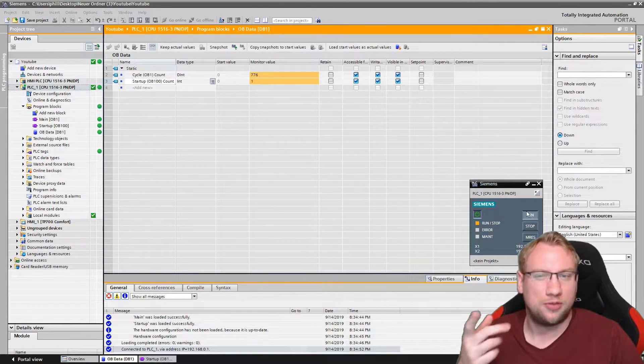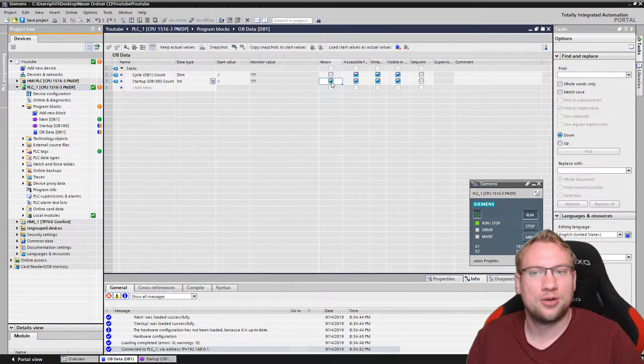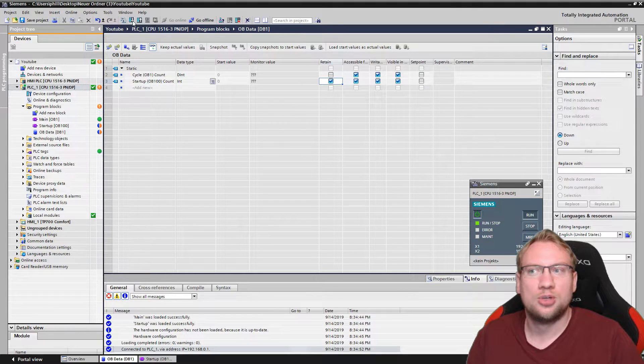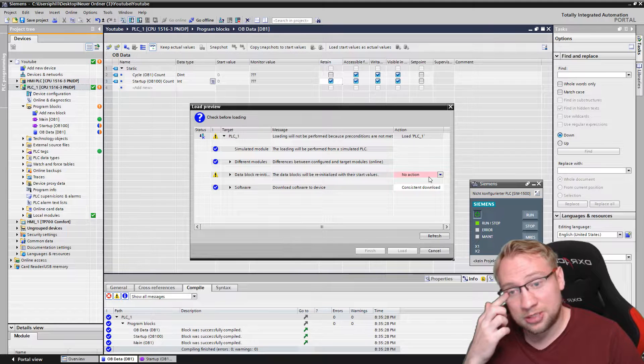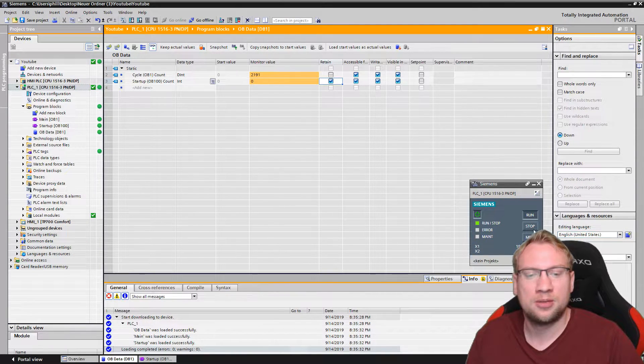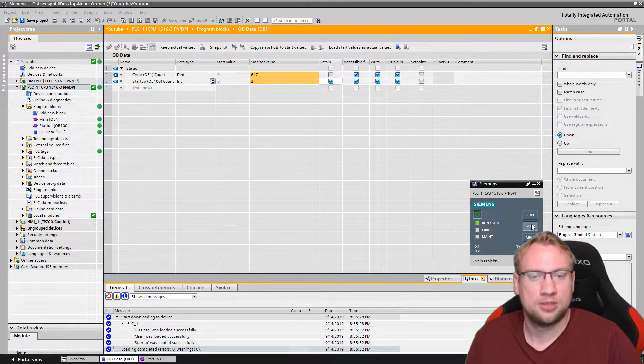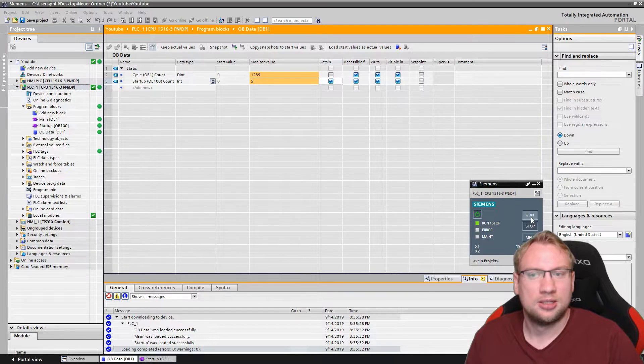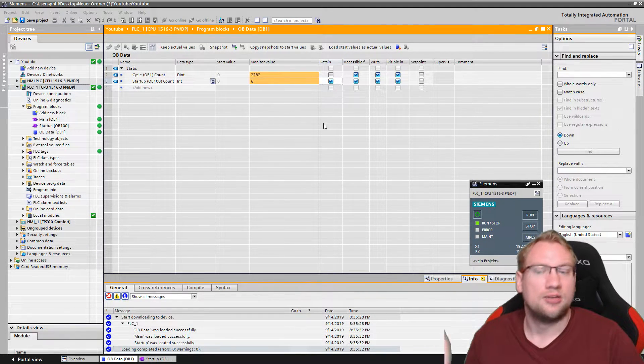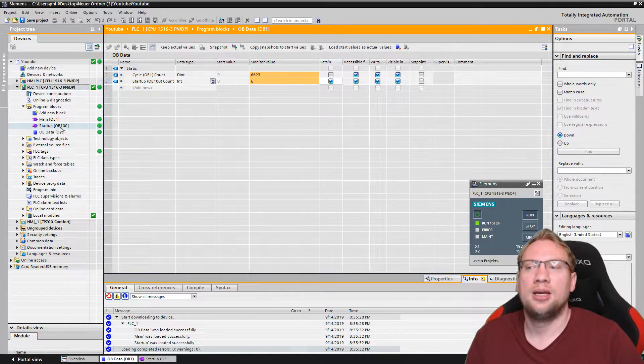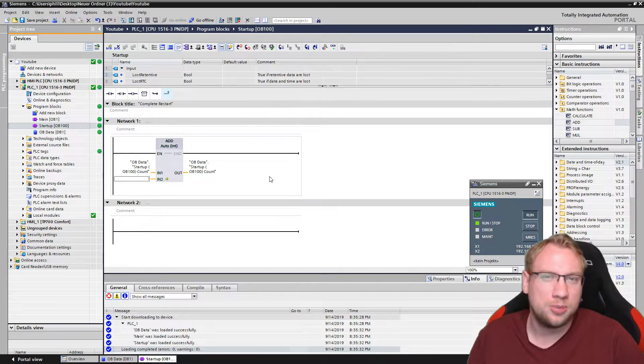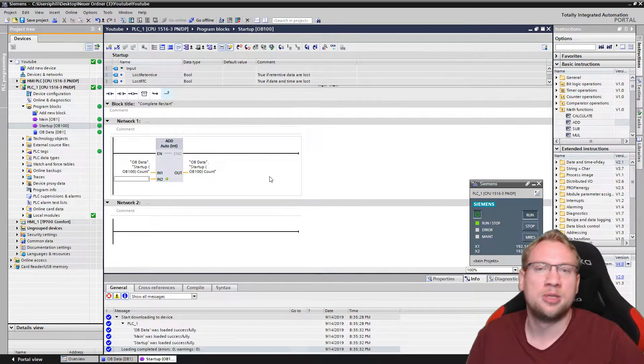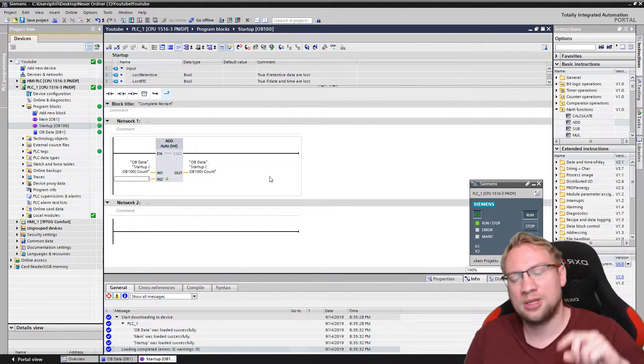To avoid this, for now, I will talk about retaining values later on. I will just turn on this retain thingy here, which actually restricts the PLC to reset this variable, and it will keep the value. You see, three restarts, four restarts, five restarts, six restarts. That's it. Now I only know how many times the PLC has restarted, and now I could put anything into my OB100 that I want to be executed one time and exactly at the beginning of our PLC startup.